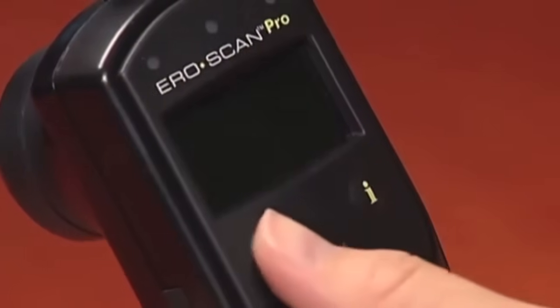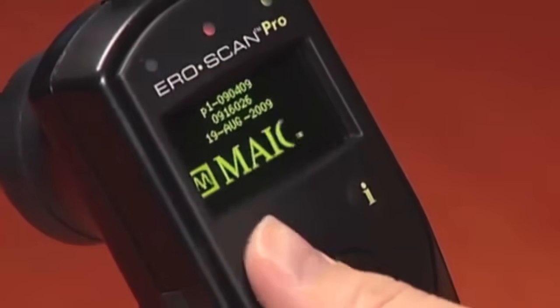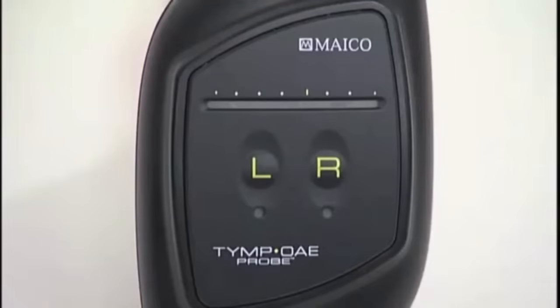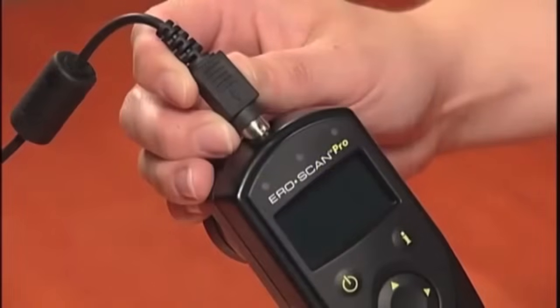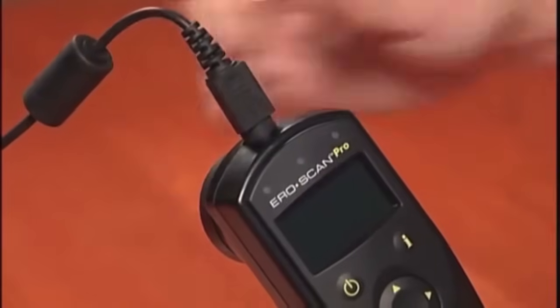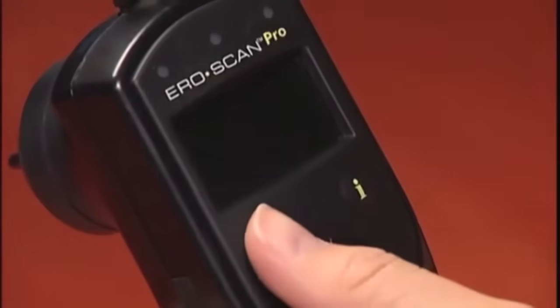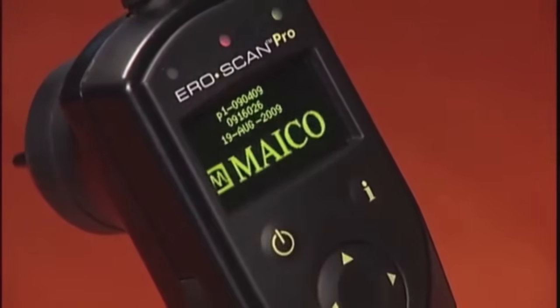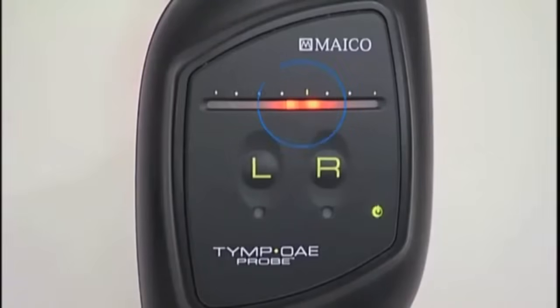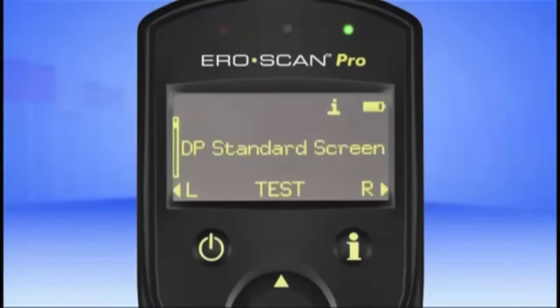If you're testing with the internal probe, simply press the power button to turn the unit on. If testing with an external probe, first connect the probe to the external probe port located on the top of the unit, and then press the power button. When the probe has been detected, the status indicator on the probe enclosure will illuminate green. All available protocols will appear in the main menu when the instrument is powered on. Please note that the tympanometry protocols will only appear in the main menu when the TYMP-OAE probe is attached and recognized by the Ero Scan Pro.